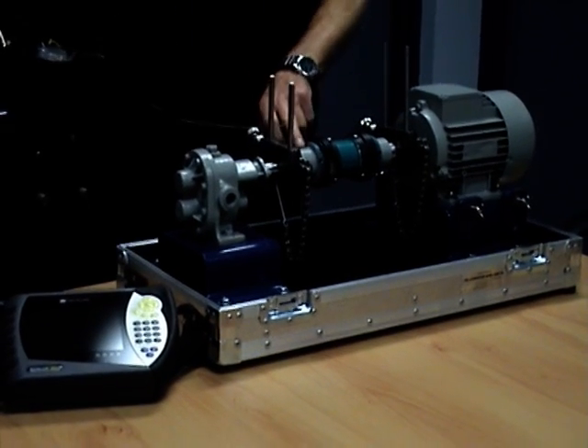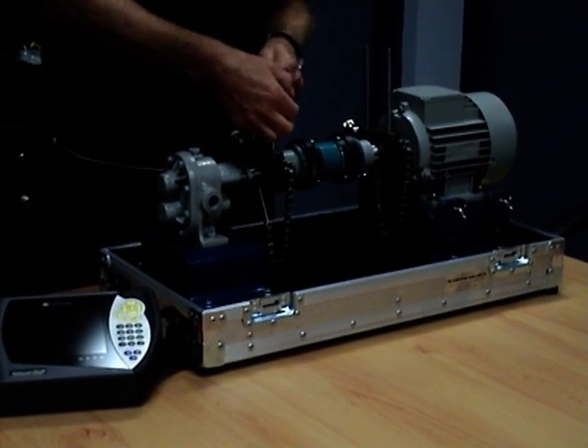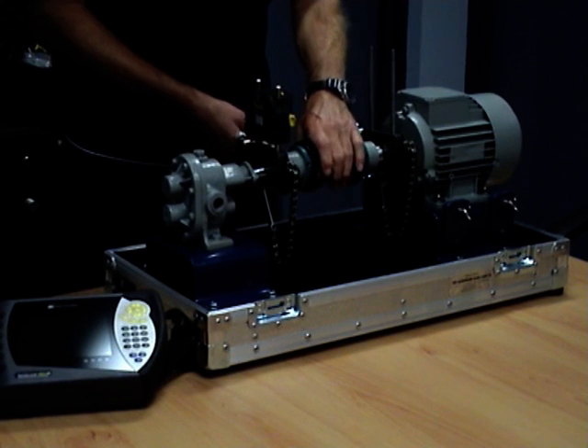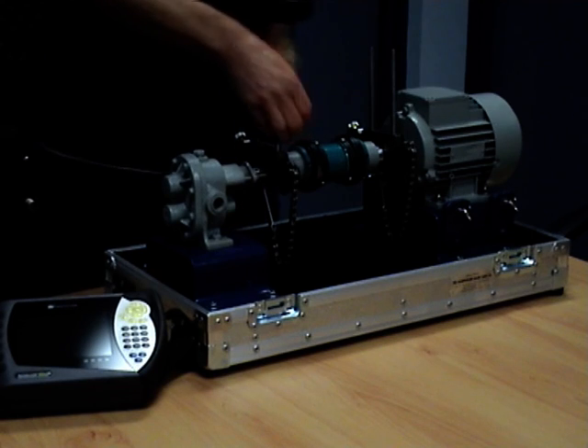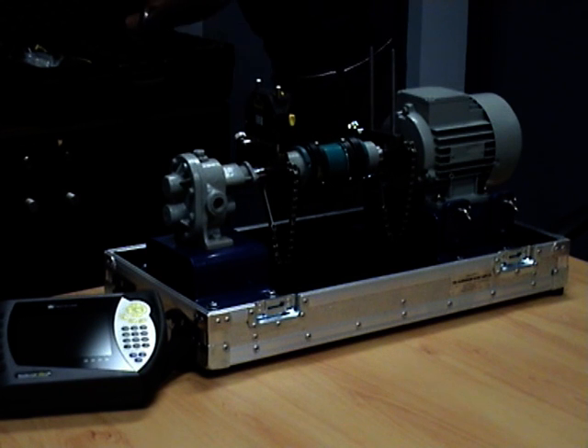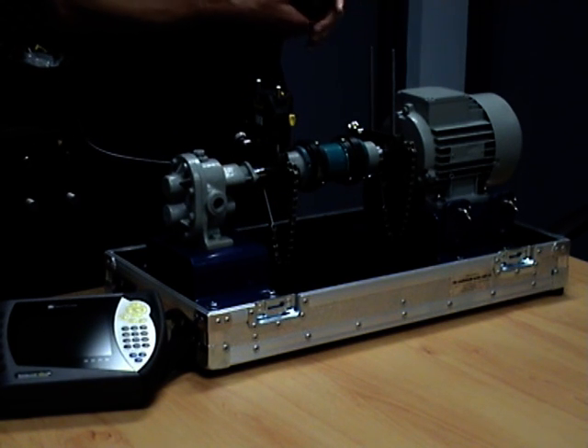So our brackets can be mounted on either the shafts or the coupling. What we're trying to do is to make the shafts collinear during operation, whether we're mounted on the coupling (this is the movable element of the coupling) or on the shafts. We've got our main components: the laser that you've got there, a receiver, and in this case the receiver's got a Bluetooth module, so it's wireless communication, and then our computer.